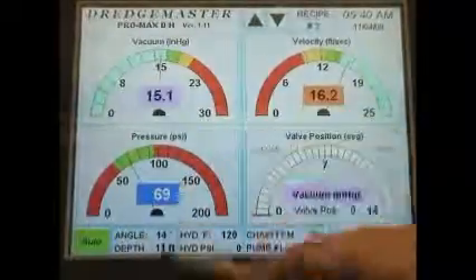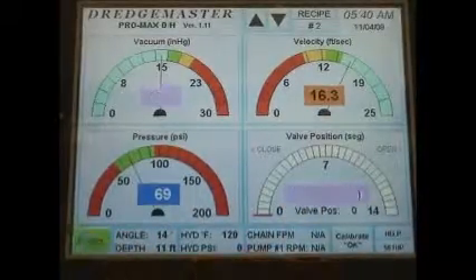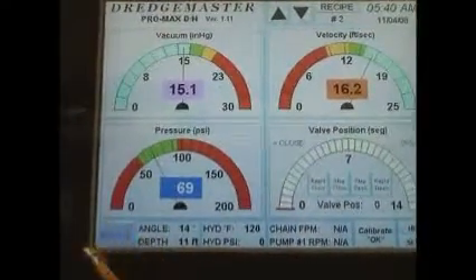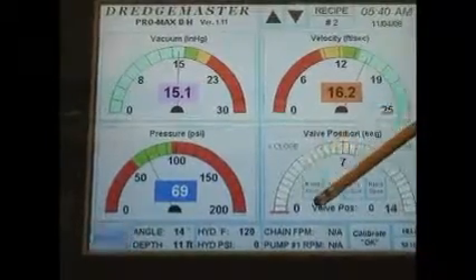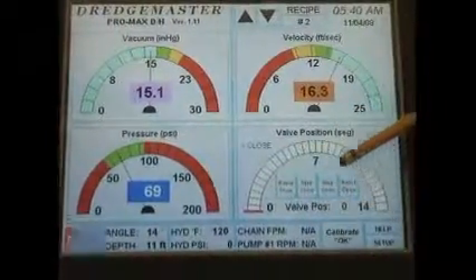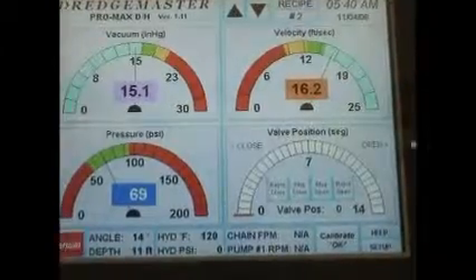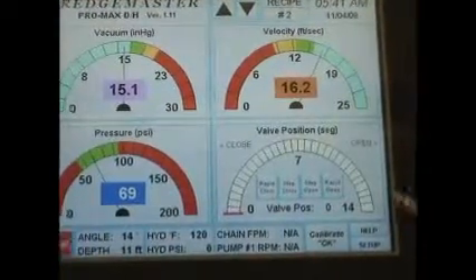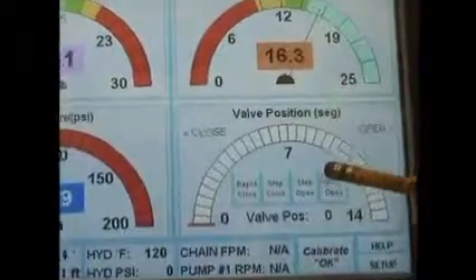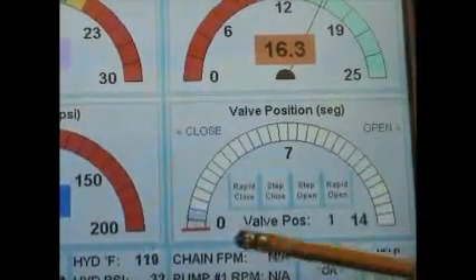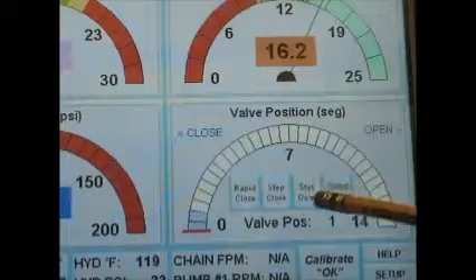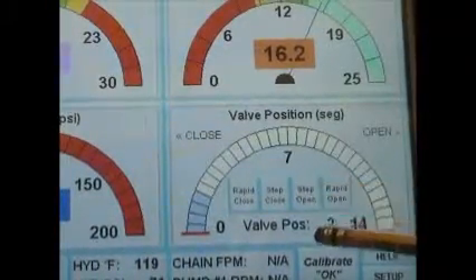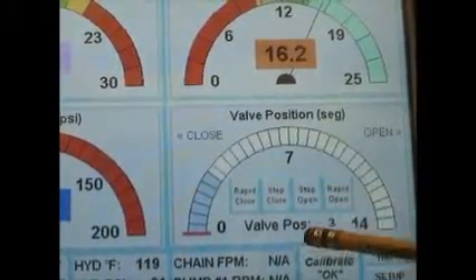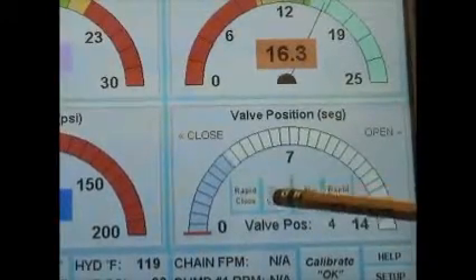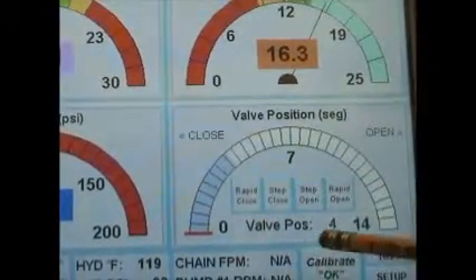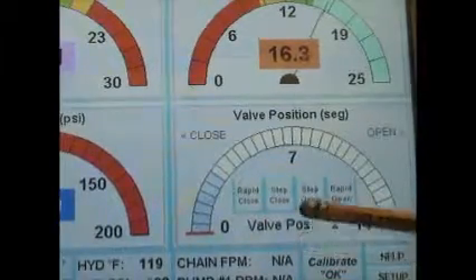If we want to open the valve manually, we're going to touch this auto button, and now we get a manual light coming on. We get 4 other buttons that now have appeared in the valve position gauge. For example, if we want to step this valve open a little bit at a time, we would simply touch step open. It opened a little bit. We can continue to step open, and we can fully open up the valve if we so choose by stepping the valve open. We can also step the valve closed by touching it and stepping the valve closed.